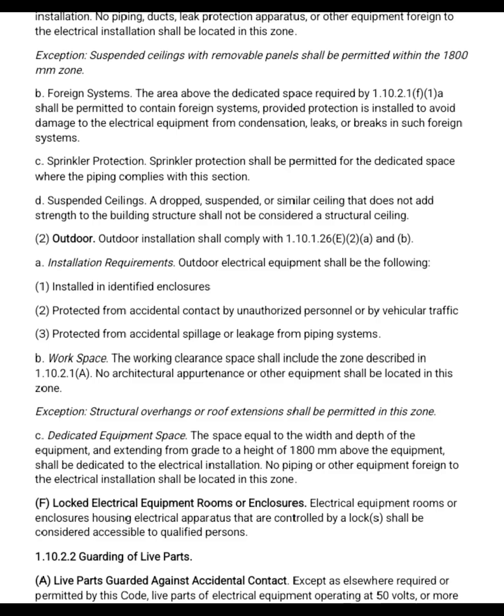C. Sprinkler protection. Sprinkler protection shall be permitted for the dedicated space where the piping complies with the section. D. Suspended ceilings. A dropped, suspended or similar ceiling that does not add strength to the building structure shall not be considered a structural ceiling. Number 2. Outdoor. Outdoor installation shall comply with 1.10.1.26 E2A and B.